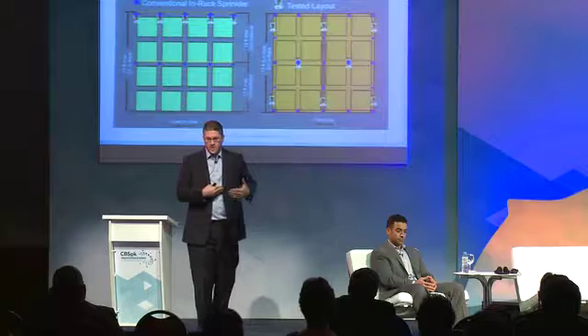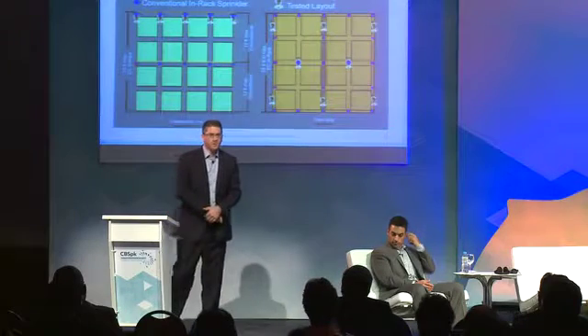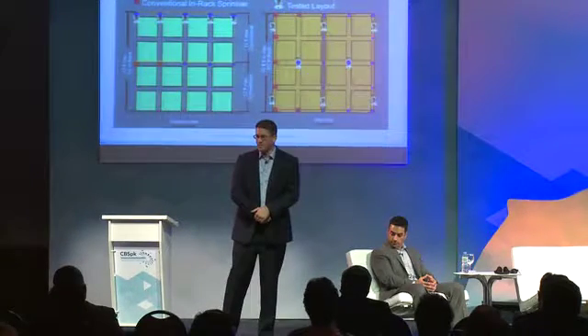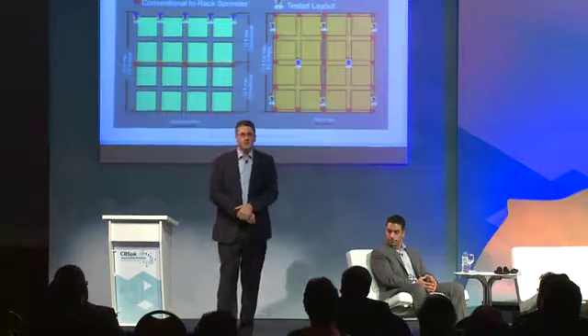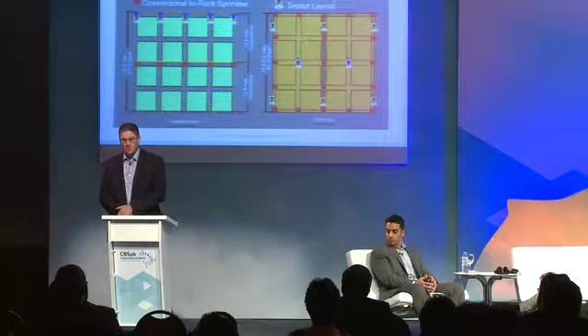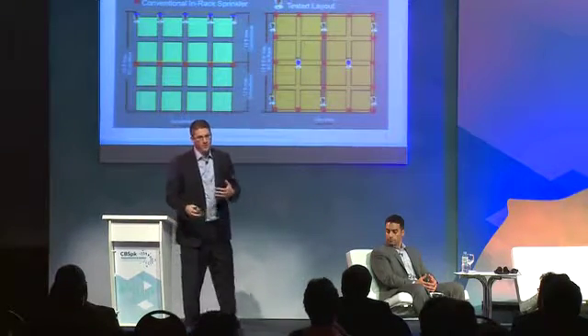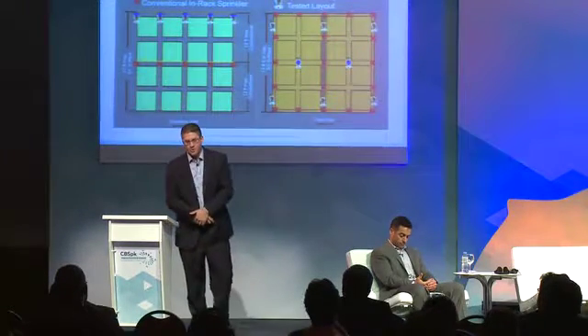Multiple row rack, there has been some testing done out to about a 4 pallet deep multiple row rack. And that one also spaces out the sprinklers farther, puts some a little bit inboard of each face, again every other, and then staggered with sprinklers in the center flue, also at every other transverse flue space. Eliminates an awful lot of sprinklers from the job. You eliminate essentially 1 out of every 5 on each in-rack level. And on top of that, the in-rack levels get spread apart from about 3 meters up to about 6 meters for expanded uncartoned commodity, and even farther apart, 9 meters for cartoned commodity.